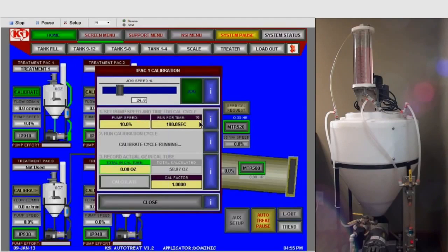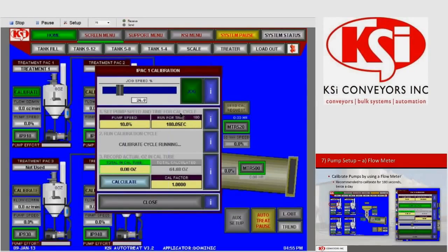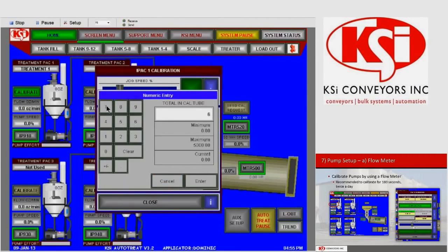As you can see, we're at 15 seconds, counting down. As soon as that's done, the pump will stop, and at that point we'll read what the cal tube says and enter that in. Okay, it has stopped, and if we look at the cal tube, it shows 67. The calculated amount was 64.68. So we'll put in 67, press enter.